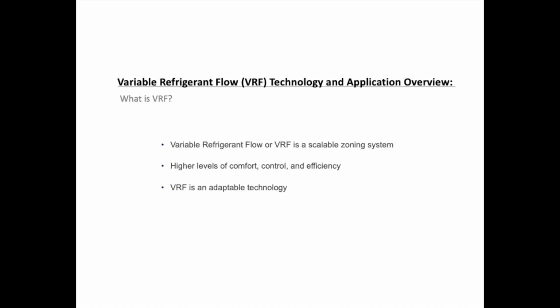First of all, what is VRF? VRF stands for Variable Refrigerant Flow, and it is a scalable zoning technology. VRF can provide higher levels of comfort, control, and efficiency. And we do this using variable speed compressors in our outdoor units and EC motors in our indoor fan coils.